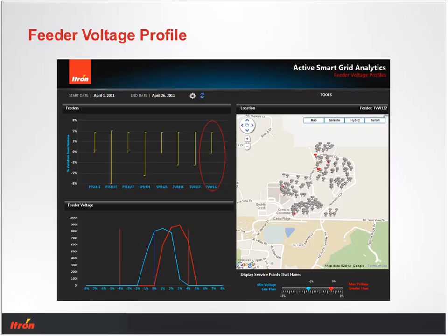On the right-hand side, we've got a map showing where your higher or low voltage occurrences are happening. There's a slider at the bottom that Curt will demonstrate to see the distribution of your low voltages, whether they're technically low or not - maybe 3 or 4% below nominal. You can see where those cluster - they may all be out on the end of a feeder, or all at one transformer. That can shed light on how you want to solve those voltage issues, which gives you a lot more room to move with your CVR.